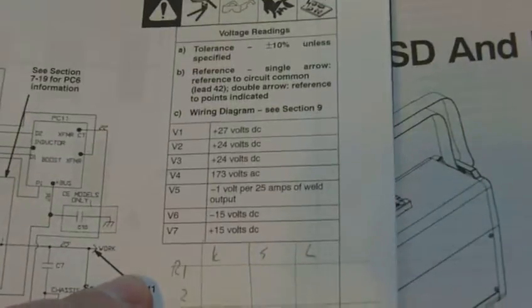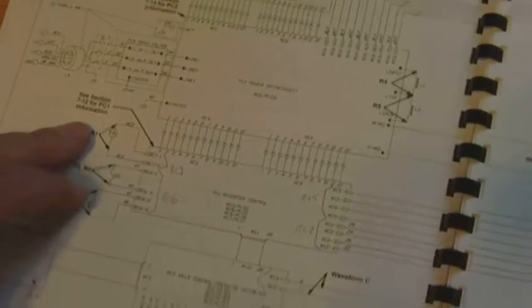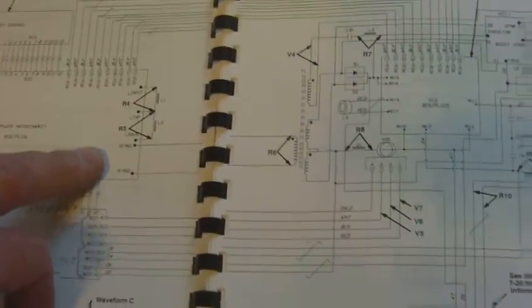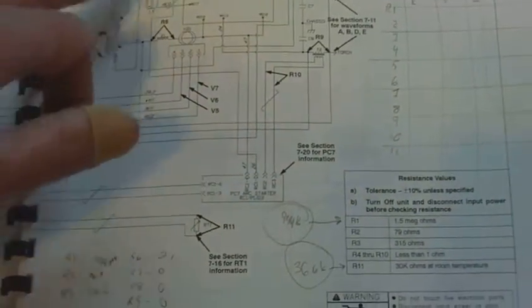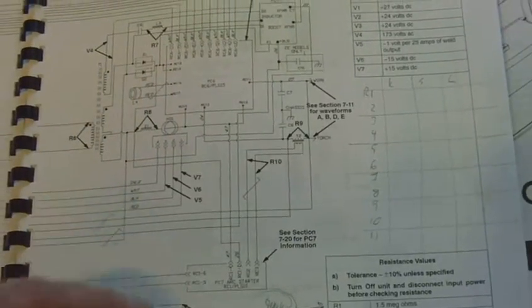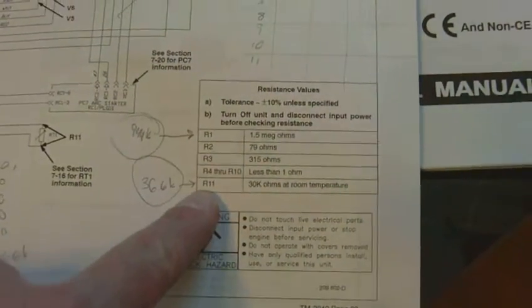Which then led to the troubleshooting circuit diagram, which is not a physical diagram, but a logical diagram, but it's neither here nor there. So basically it identifies 11 resistances that you have to check and 7 voltages. The resistances all checked out, and they're here: R1, R2, R3, R4, R5, 6, where are the others? 7, I don't know, they're on there. They all checked out just fine except for R1 and R11.